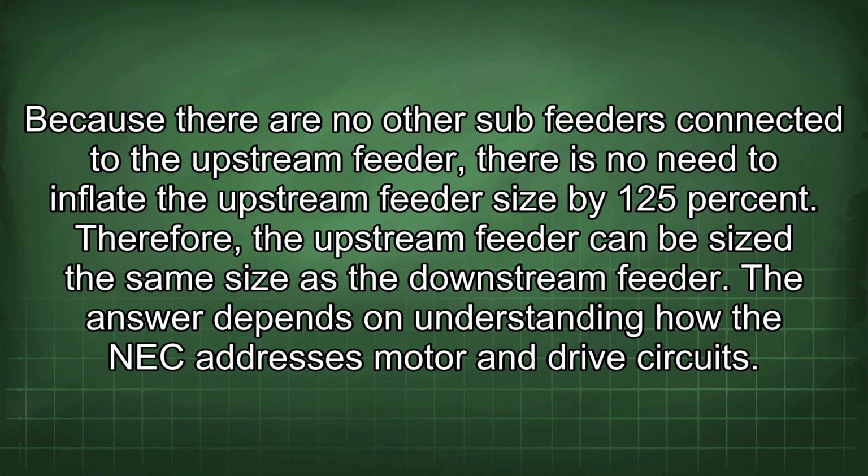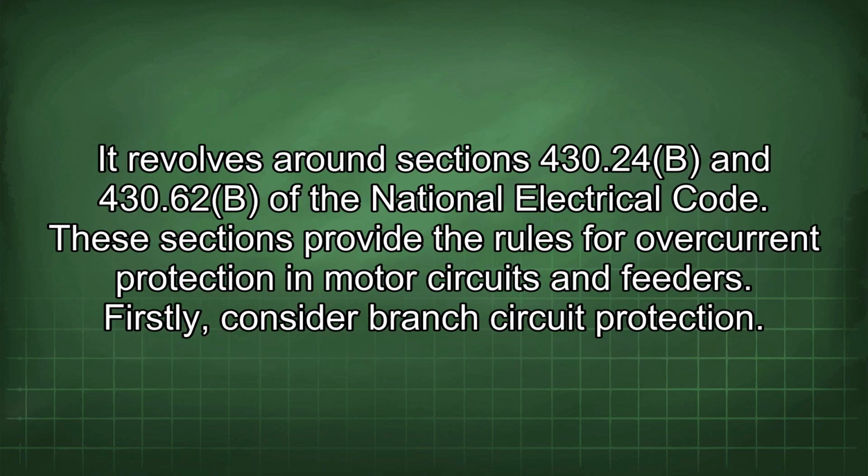The answer depends on understanding how the NEC addresses motor and drive circuits. It revolves around sections 430.24(b) and 430.62(b) of the National Electrical Code. These sections provide the rules for overcurrent protection in motor circuits and feeders.